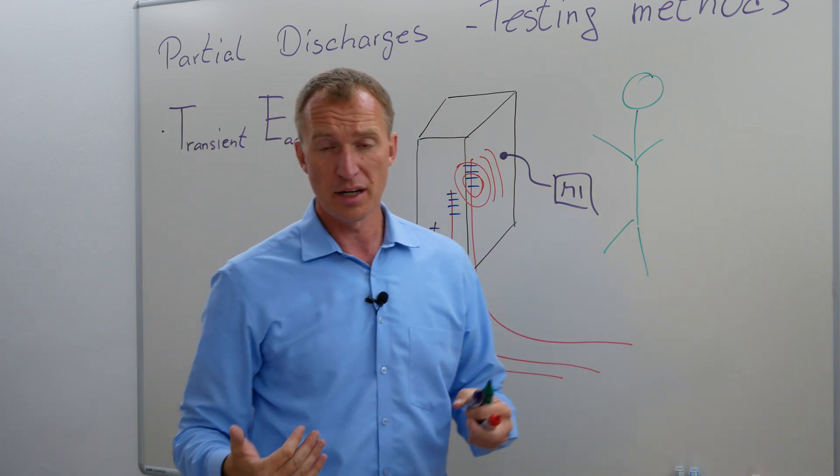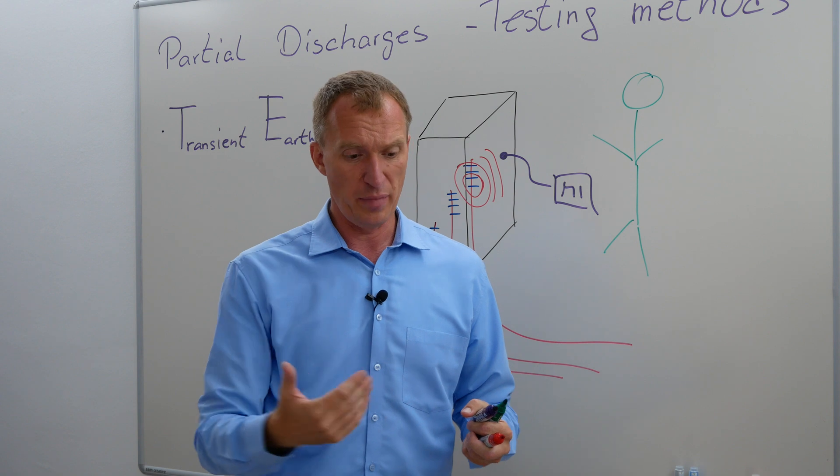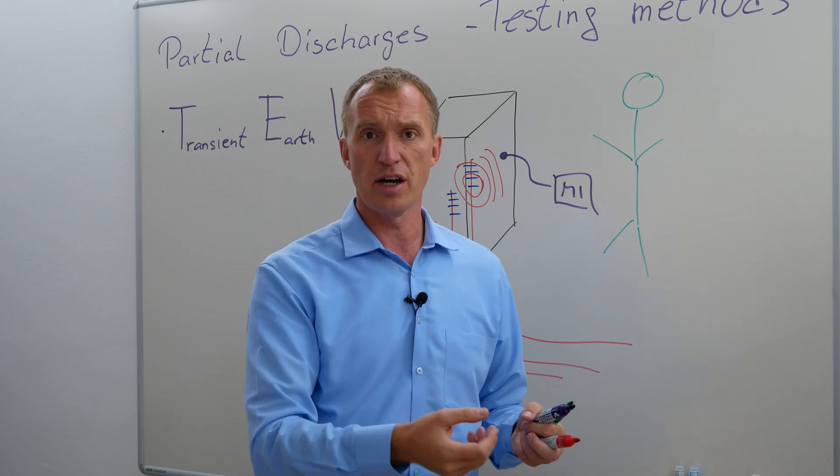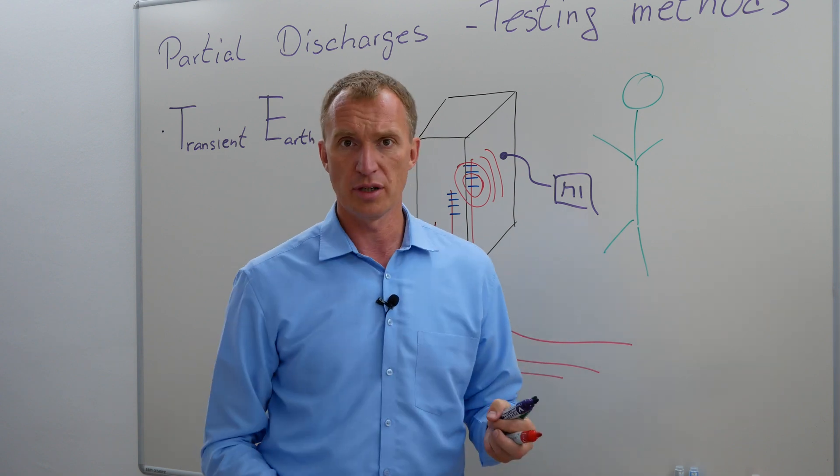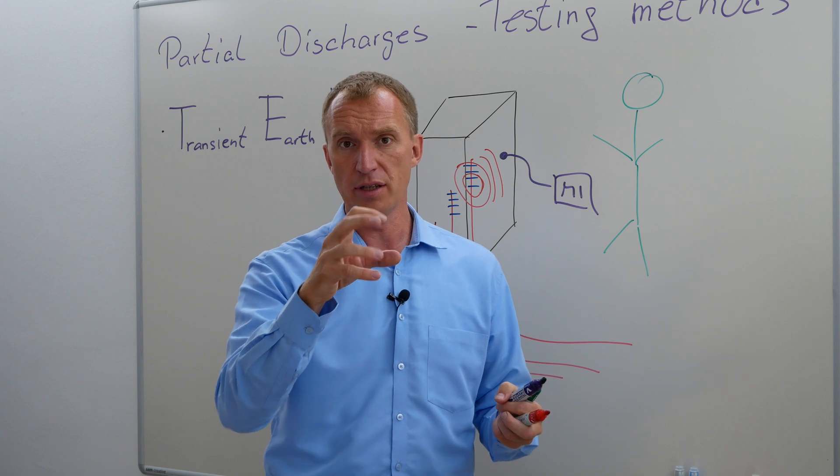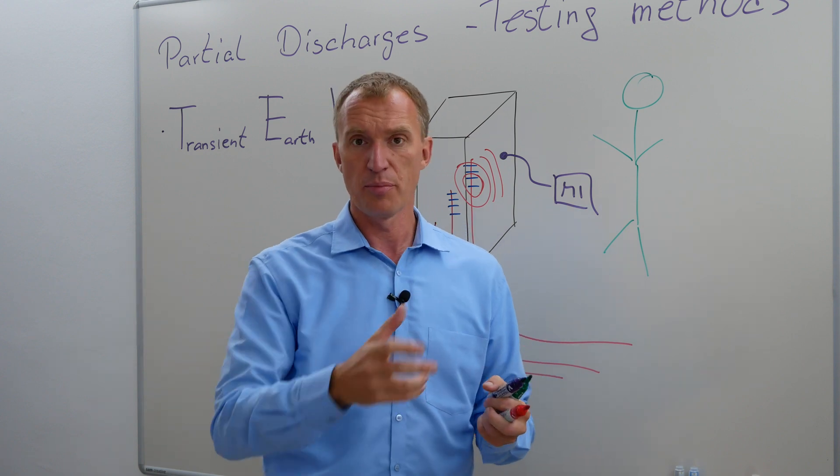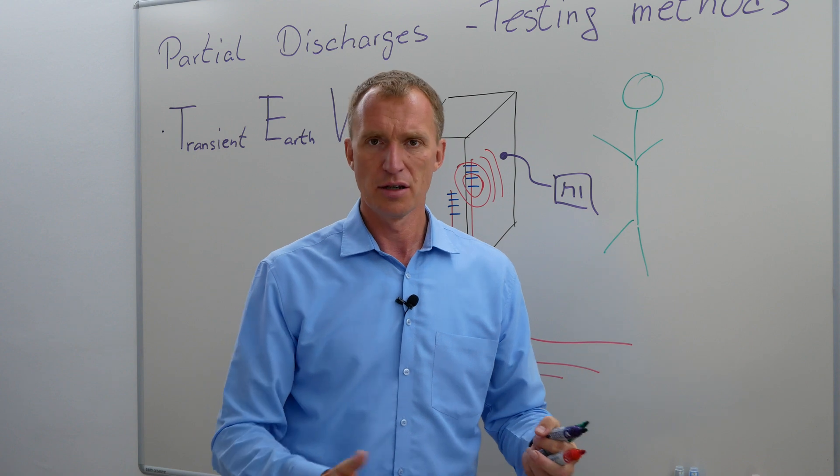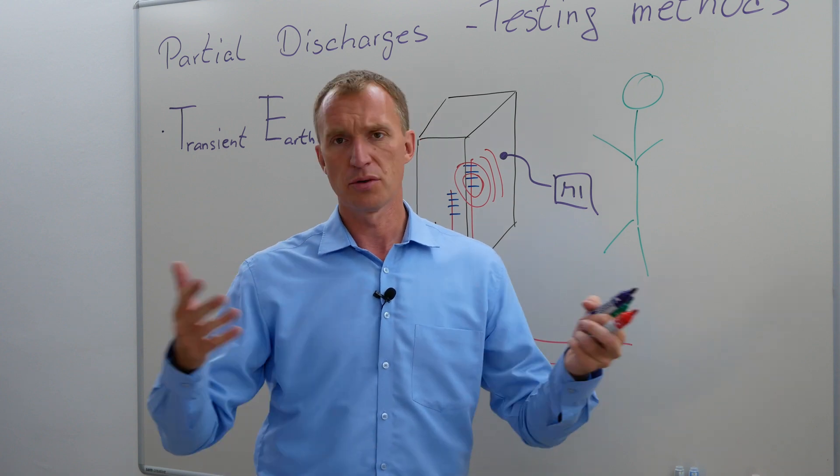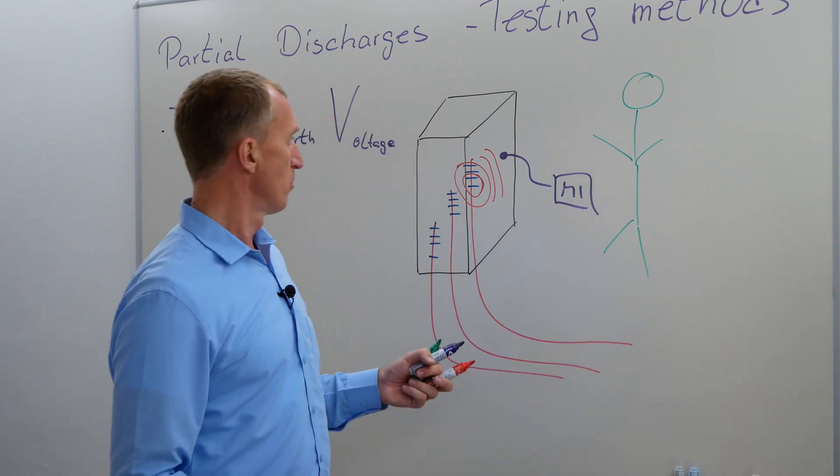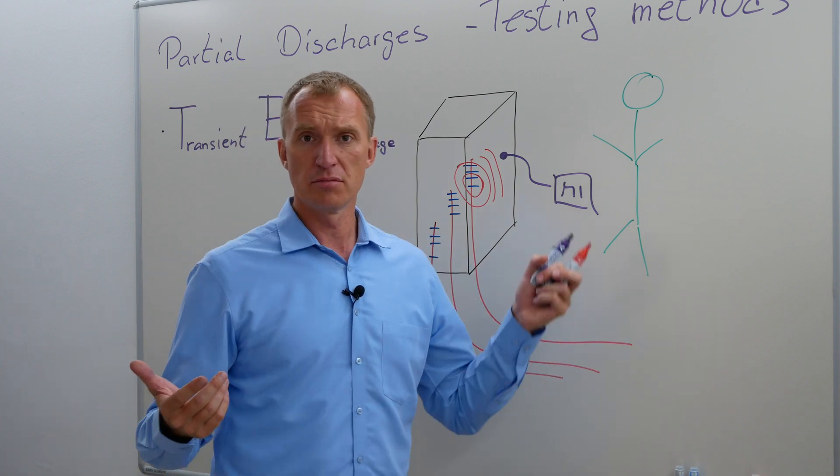If I own a substation and I want to know that, I would make an experiment and say, okay, what happens if I have a big partial discharge on my end termination? How would my TEV, my transient earth voltage sensor, pick that up? Then you have at least a sensitivity check, right? So you can place multiple on there, you can do monitoring. I think it's a pretty good idea to do that.